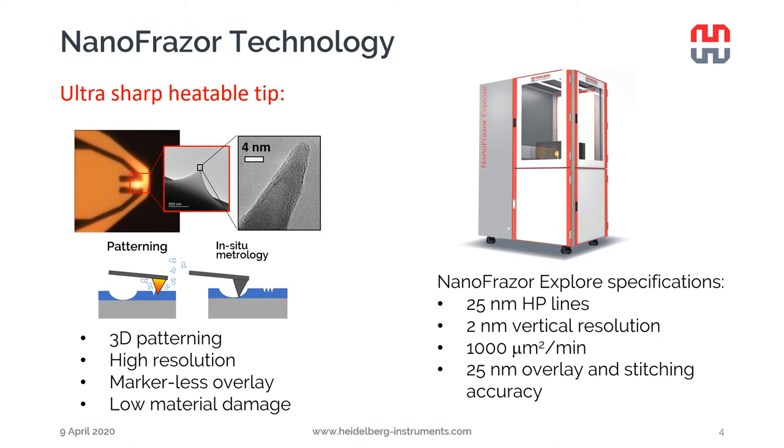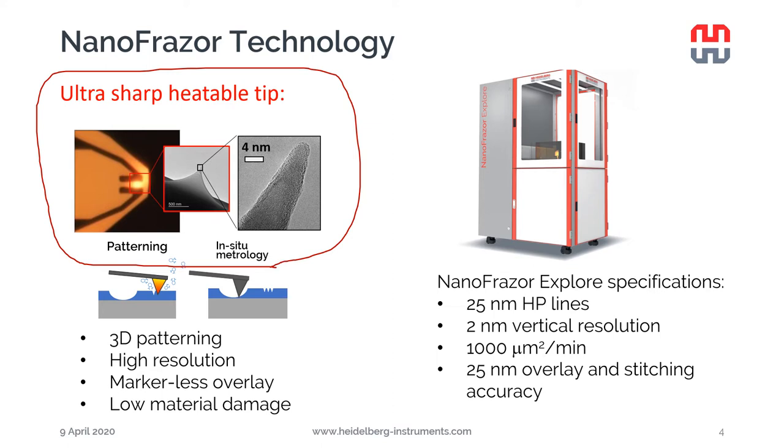If you have seen some of our previous webinars, you know that the NanoFrazor has an ultra-sharp heatable tip that can be heated up to 1300°C and has an apex diameter down to 4 nanometers. This tip can be used for patterning and in-situ imaging, which allows for 3D patterning because we can control the depth at which we push the tip, and with in-situ metrology we can check how the patterning is going and adapt the parameters to match the target topography.